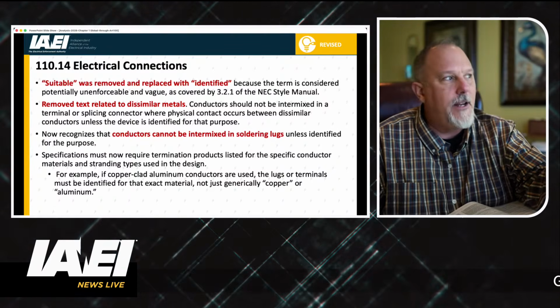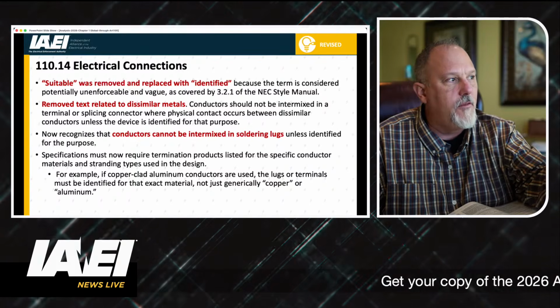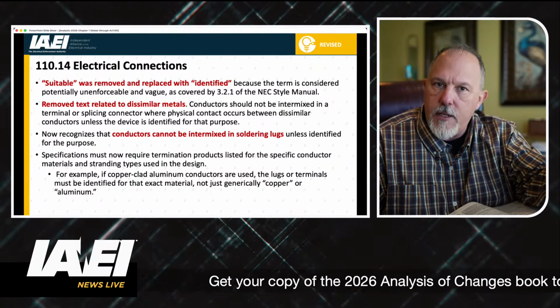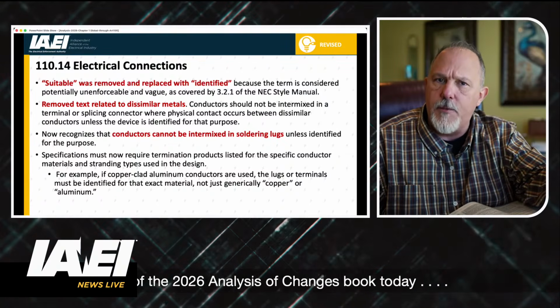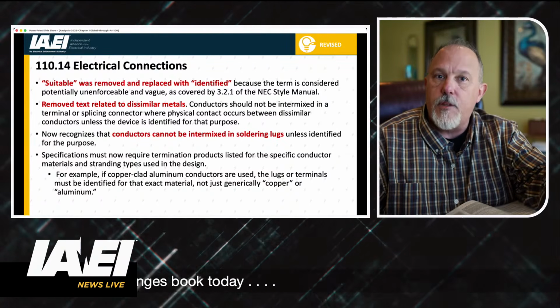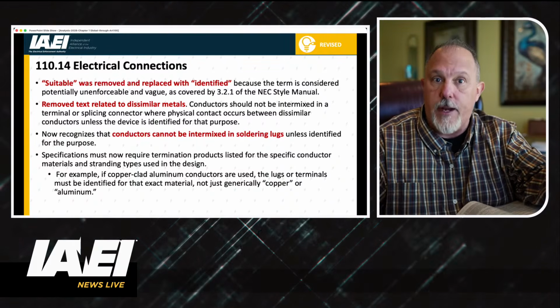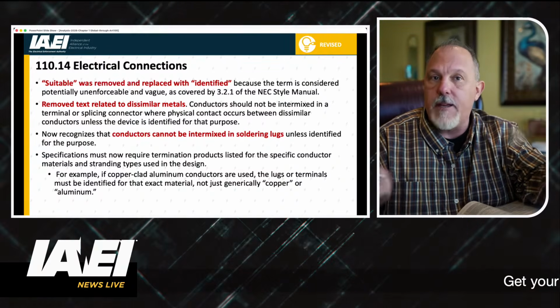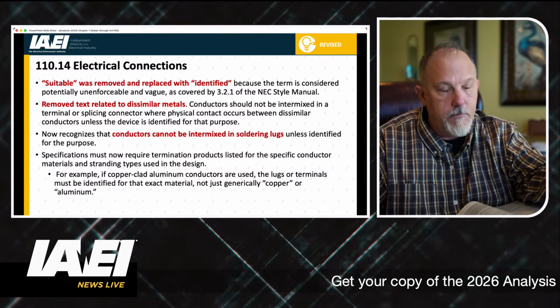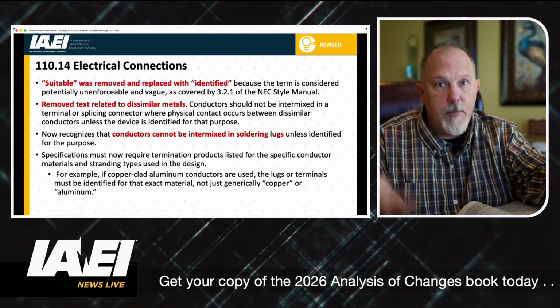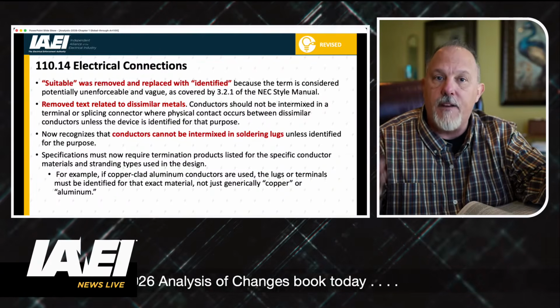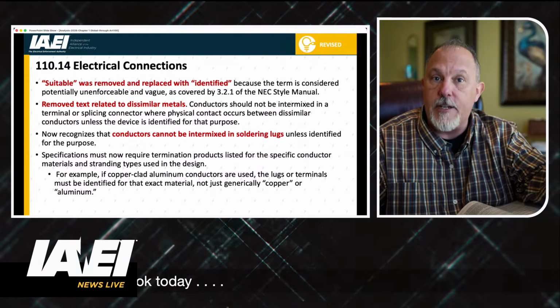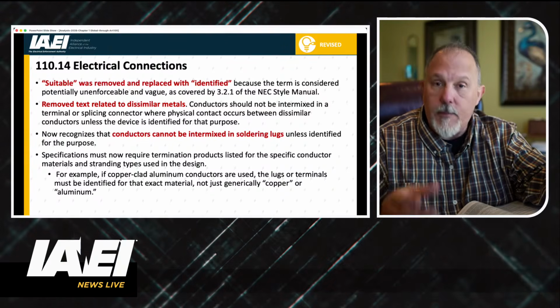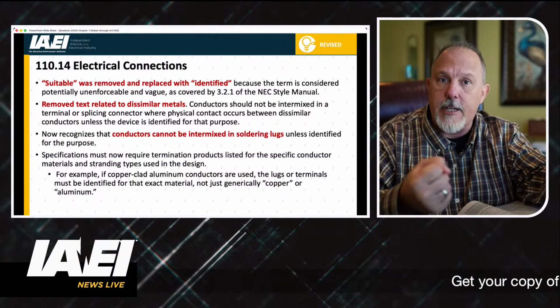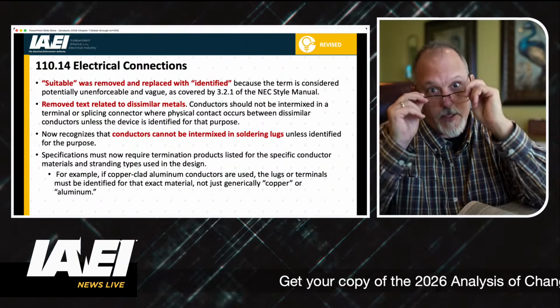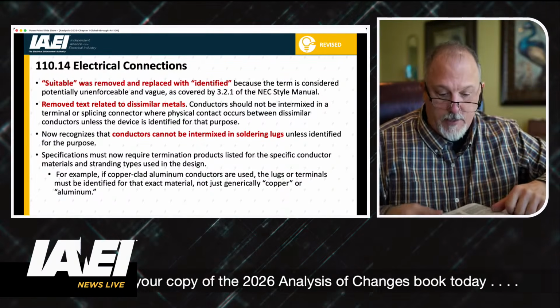And I don't know what the industry movement was, I don't know if it was in the PV industry. They were using more flexible cables, which the flexibility comes from the number of strands. If I fine strand something, I could make that cable real easy to maneuver. But when I terminate it, I need to make sure that I have a terminal that can handle the fine stranded nature of the conductor itself. And because we want a good, solid connection, you don't want it to be a bad hair day when all the frizz goes everywhere.